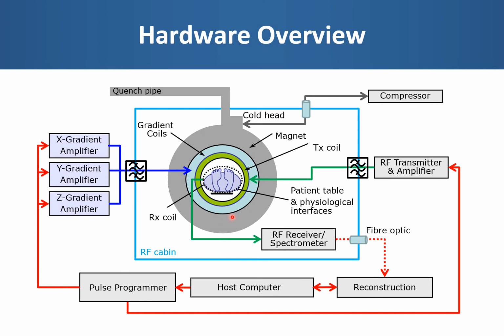Because liquid helium is quite expensive, there is normally a cold head or cryocooler mounted on the magnet. This is a very high performance refrigerator that works to keep internal radiation shields inside the magnet assembly very cold to try and minimize the helium boil-off. The cold head is connected via helium lines through a waveguide in the RF cabin into a compressor in a separate equipment room.